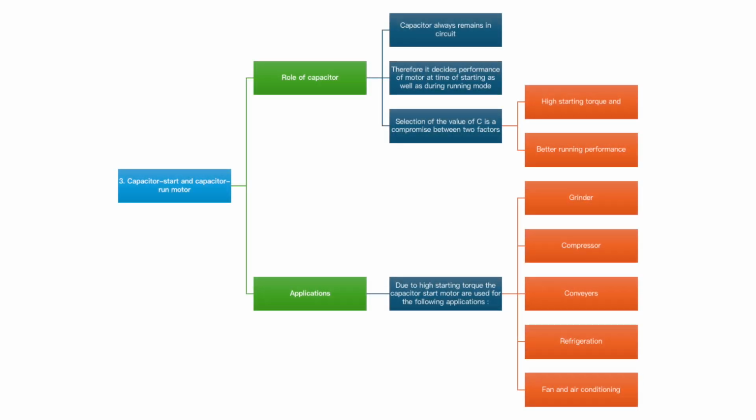The two capacitors are connected in parallel at starting. In order to obtain a high starting torque, a large current is required. So, the capacitive reactance X in the starting winding should be low, as the value of Cs should be large, where Cs is our starting capacitor.